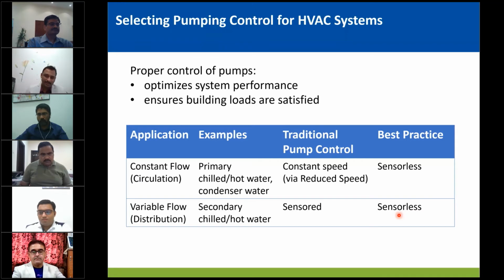For example, the building is occupied for, let's say, 5 floors, and the client decides to build another floor on top of it, or let's say the last floor was not occupied and now it's getting occupied. When something changes in the system, flow requirement also changes, which means your sensor placement also should be changing. But with the smart pumps, you can actually simulate that control curve that is equivalent to replacement of the sensor, so the new sensor position.